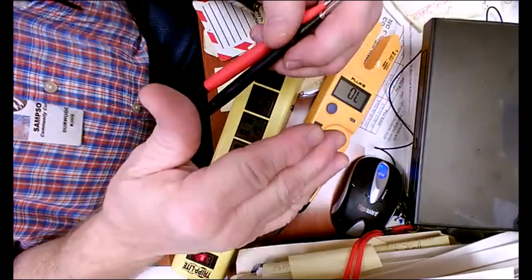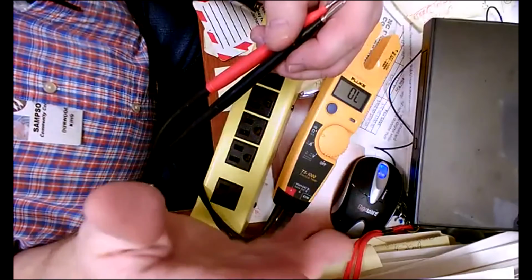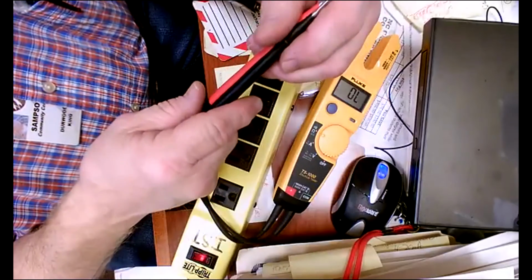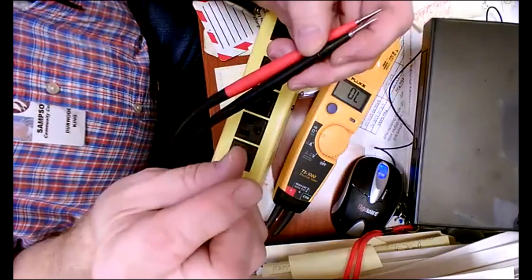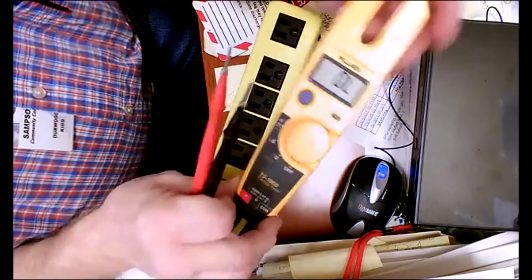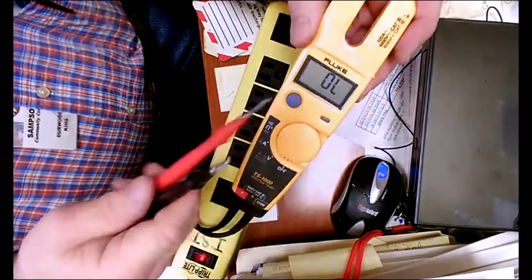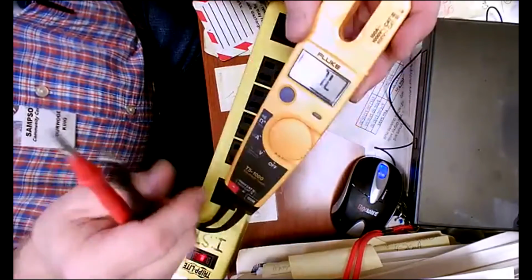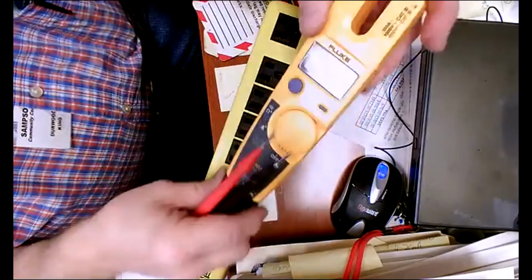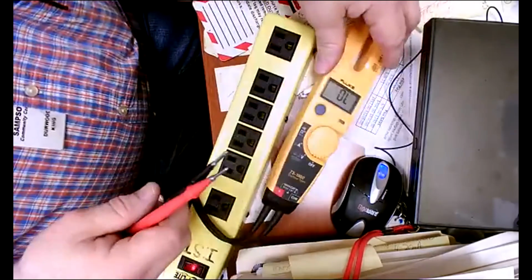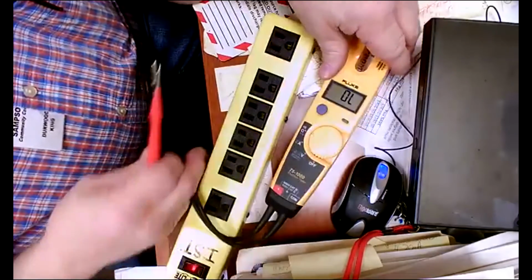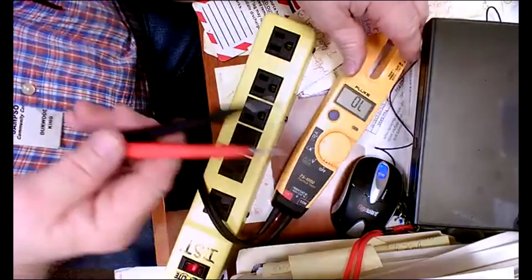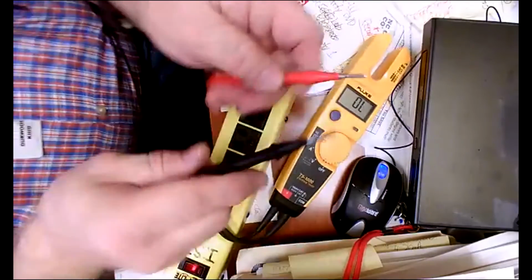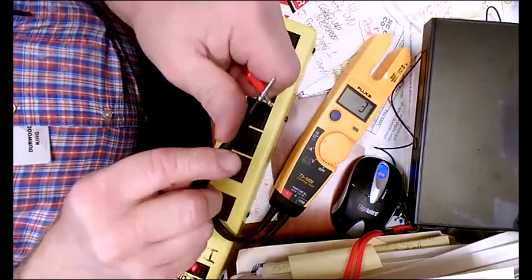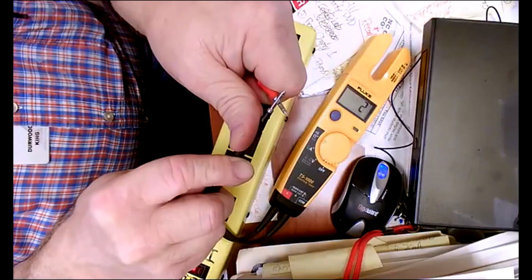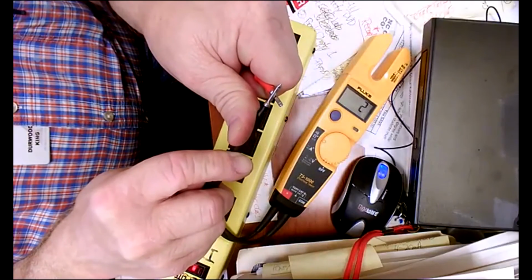When you're reading around 120 volt and up, it's not going to make much of a difference. It's not going to hardly affect you. If you're doing low voltage readings, low voltage DC readings, it may affect it a little bit more, but it's still not going to be a major issue with 2 ohms. But if you got 5, 6, 7 ohms, it's a concern. You really need to be replacing your test leads. That's what I'll do every morning.